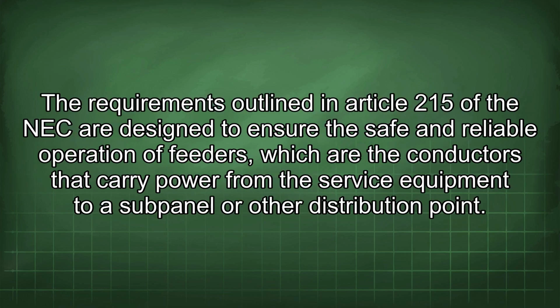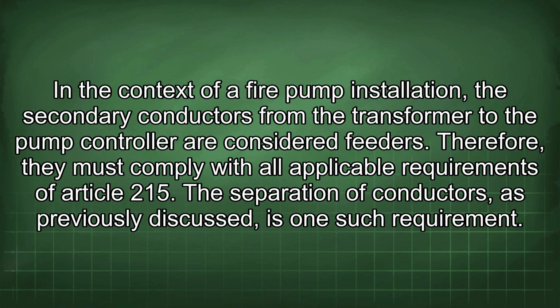The requirements outlined in Article 215 of the NEC are designed to ensure the safe and reliable operation of feeders, which are the conductors that carry power from the service equipment to a subpanel or other distribution point. In the context of a fire pump installation, the secondary conductors from the transformer to the pump controller are considered feeders. Therefore, they must comply with all applicable requirements of Article 215. The separation of conductors, as previously discussed, is one such requirement.